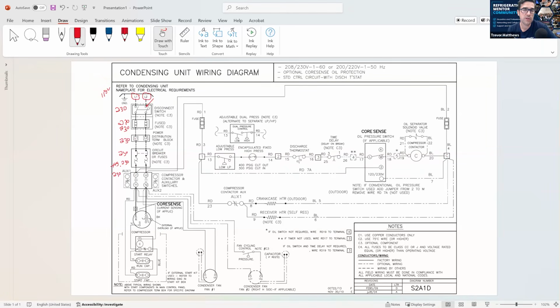Understanding everything that's on your map. This is your electrical map. It's so important. De-energize, auxiliary 1, we got auxiliary 1, we got auxiliary 2. So auxiliary 1, if we look for it on here, because this is our compressor contactor in real life, compressor contactor auxiliary, right here, auxiliary 1, and what is that connected to? That is connected to the crankcase heater, which is right here. So that crankcase heater is showing us the crankcase heater as well as this receiver heater.